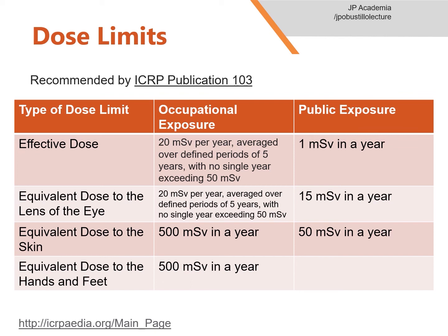Let us review the dose limits. For effective dose under occupational exposure, the limit is 20 millisieverts per year, averaged over a defined period of 5 years, with no single year exceeding 50 millisieverts. For public exposure, the effective dose limit is 1 millisievert per year. Note that for occupational exposure, if the worker declares pregnancy, the dose to the embryo or fetus should not exceed approximately 1 millisievert during the remainder of the pregnancy.